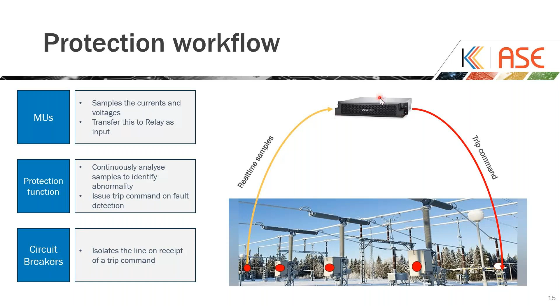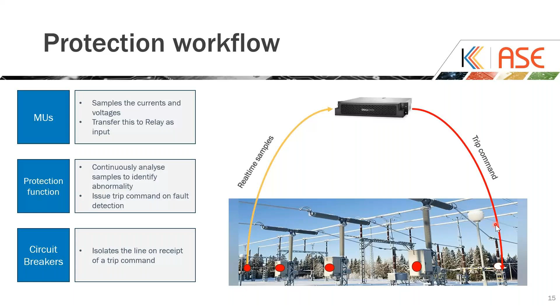So here we have a protection workflow, in the scenario where samples of the current and voltages are received from the merging unit. The protection function, running in server hardware or something like this, continuously analyzes the samples. Multiple virtual protection relays can be running here, and whenever a VPR identifies an abnormality, it sends a trip command to the field. Upon fault detection, the circuit breaker in the field isolates the line on receipt of the trip command, based on the electromechanical operation. So this is a protection workflow simplified in a VPR environment.